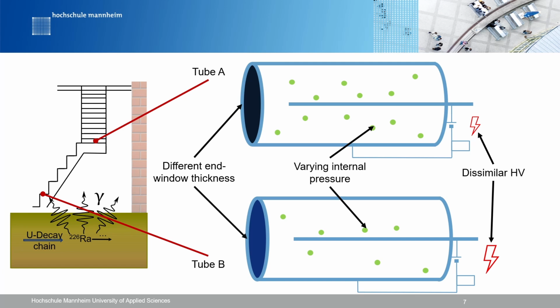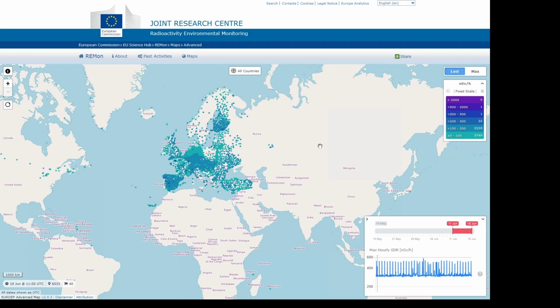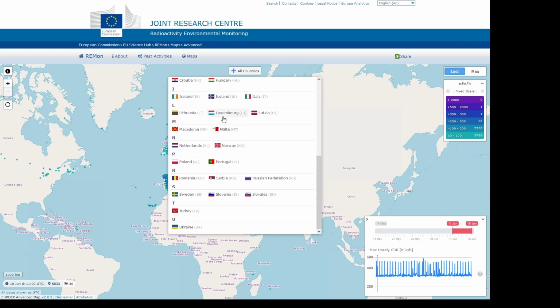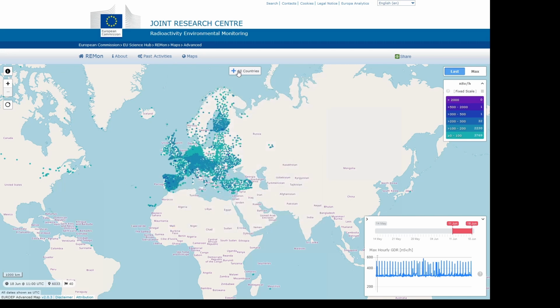In this context, the geographical location plays a significant role. Some users are confused by obtaining readings of the dose rate at their places of residence compared to the values reported by their local authorities. In many countries, real-time dose rates are available from public or private networks as a reference. Above all, you should first know what dose rate is reported. Is it the H*(10) dose rate? Or like in the Gamma Scout, the dose rate for cesium-137 equivalent.